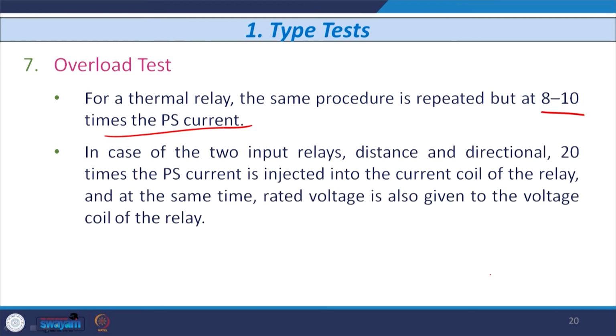So, in case of a two-input relay, that is distance and directional, again the same value as we did in case of the overcurrent relay: 20 times the plug setting is to be injected into the current coil of the relay, and at the same time the rated voltage is given to the voltage coil of the relay, and the continuous current carrying capability is to be checked.